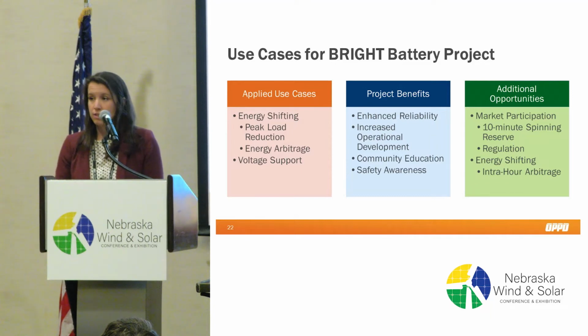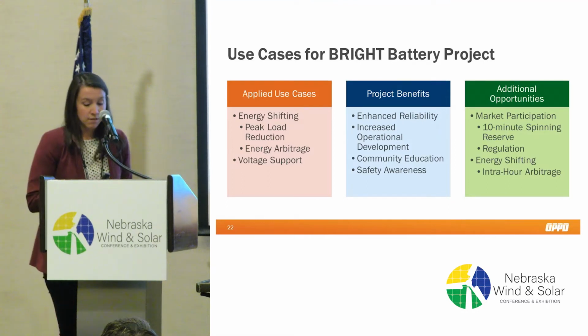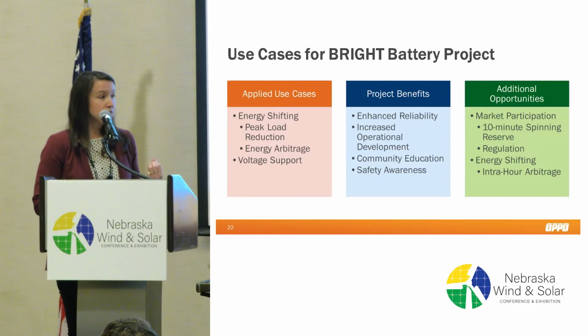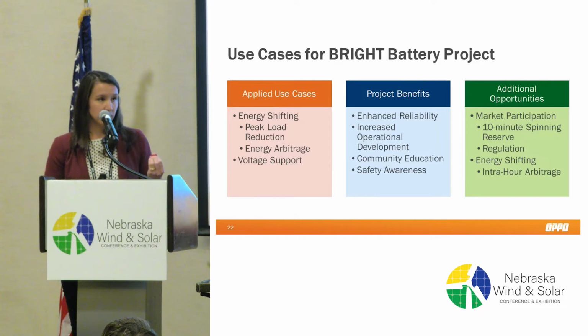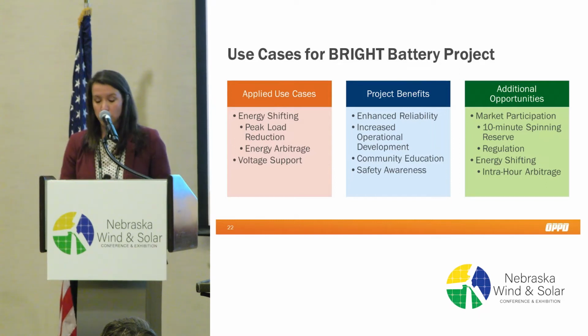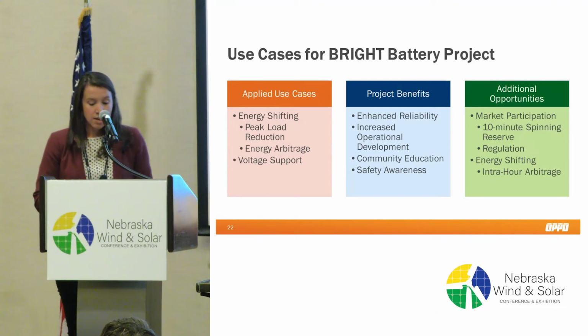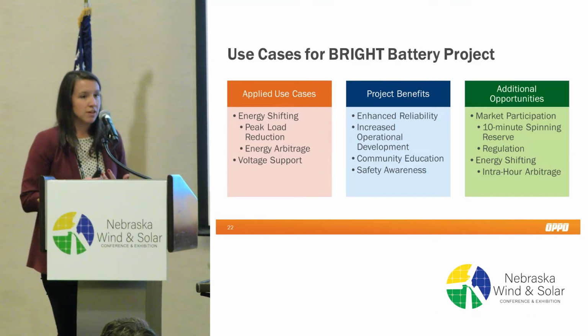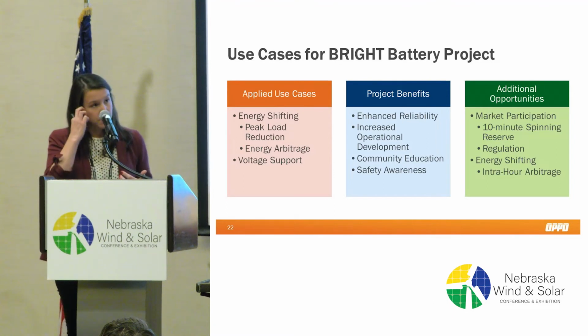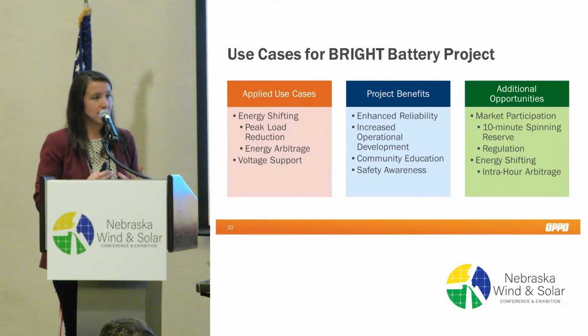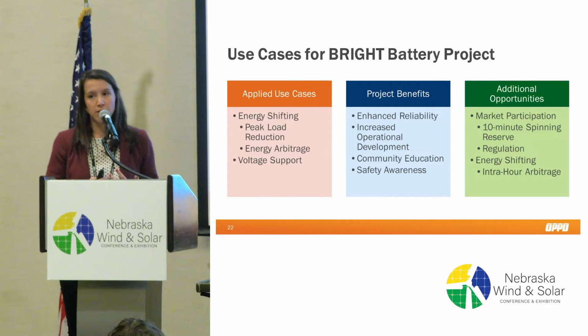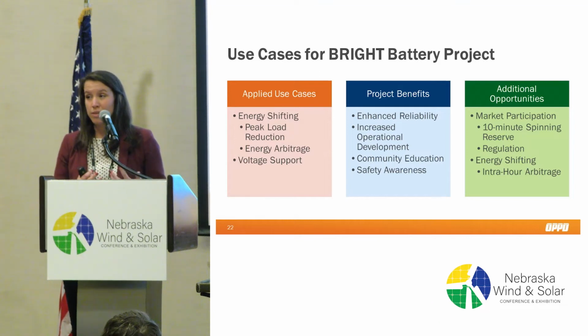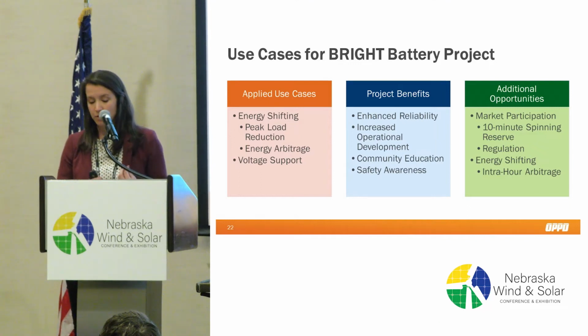Energy arbitrage is where you're charging off-peak, or at times of lower price, and then discharging on-peak. Voltage support—the inverters on the batteries have the ability to inject reactive power, which helps voltage levels on that circuit. And finally, with FERC 841, even though this is a distribution asset, we're able to start to understand how this would play in the SPP market. This is a really big opportunity to understand not only the reliability aspect, but the market dynamics of battery storage technology.